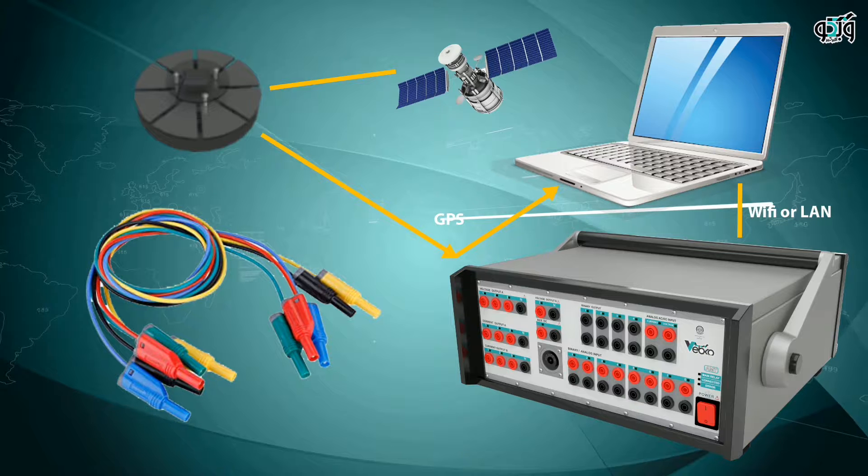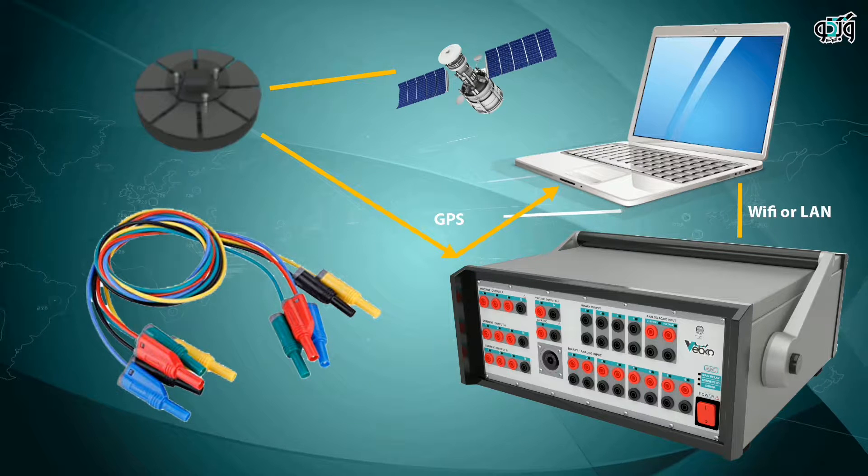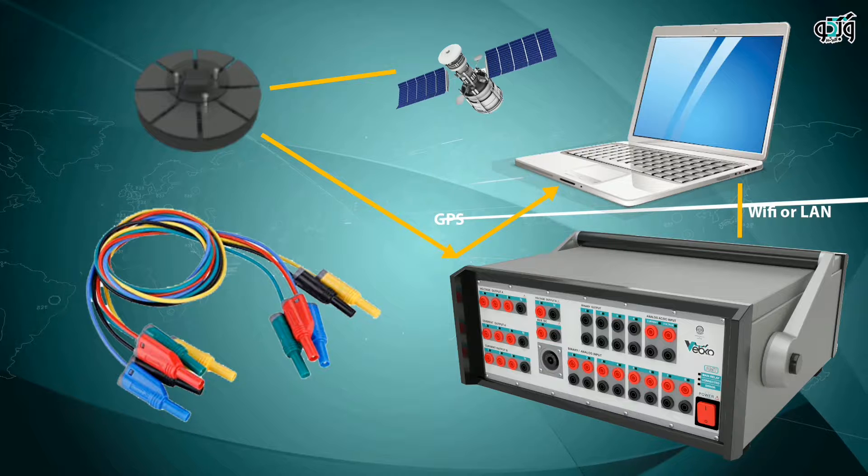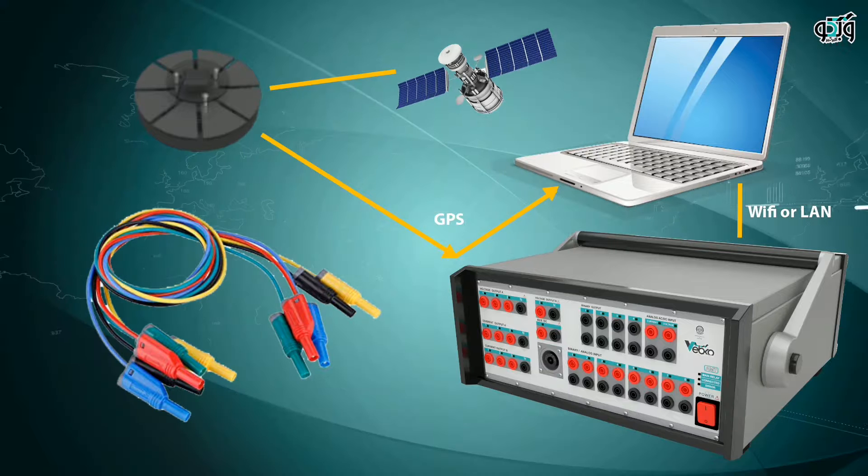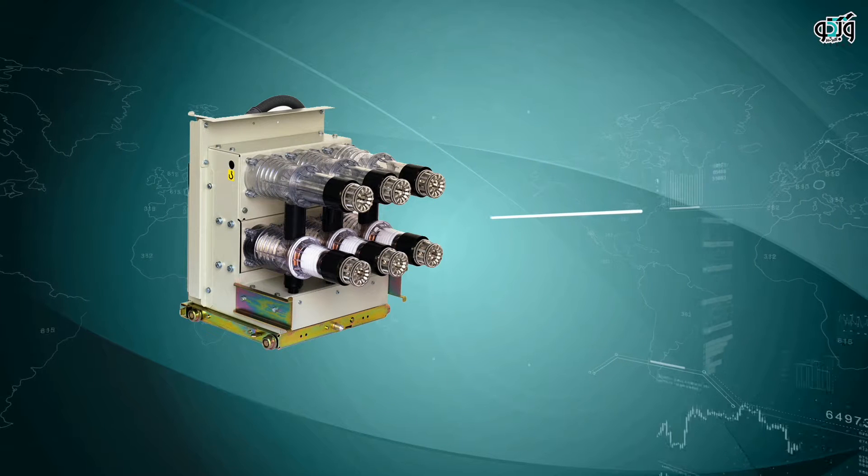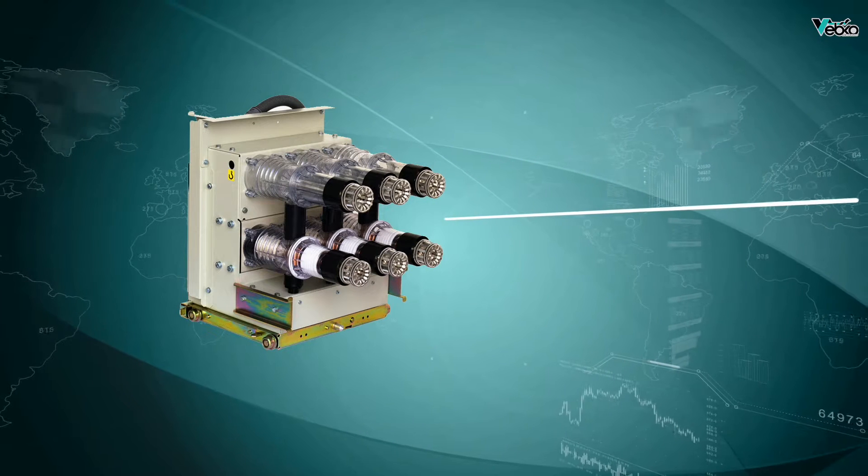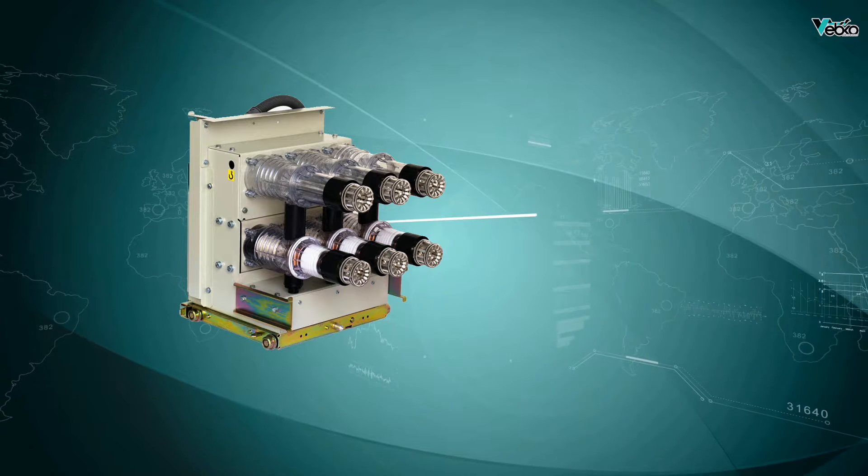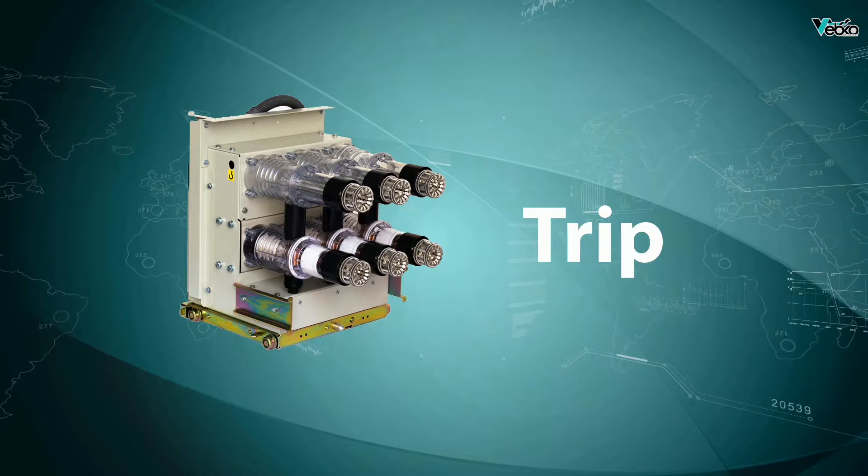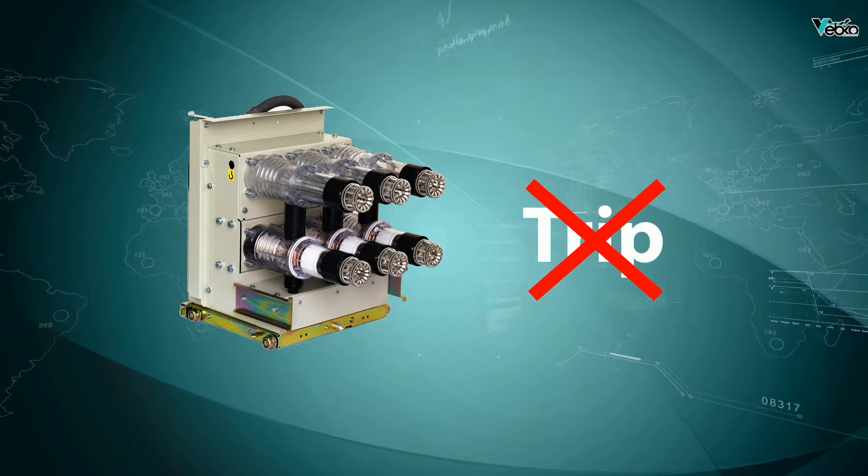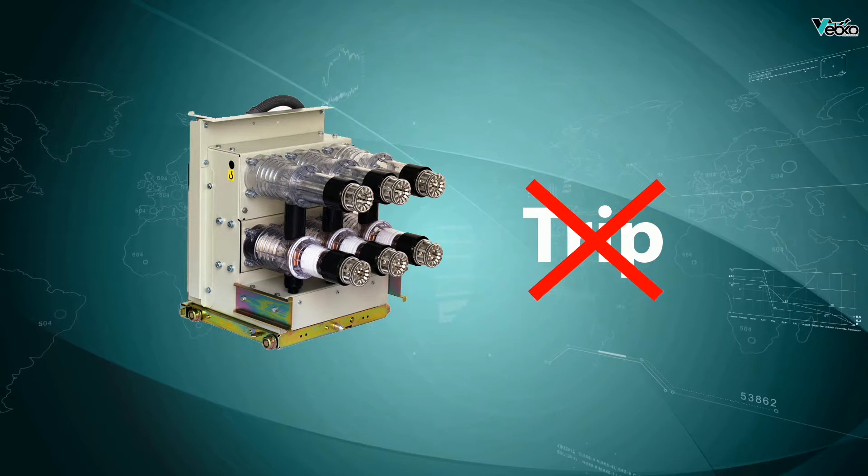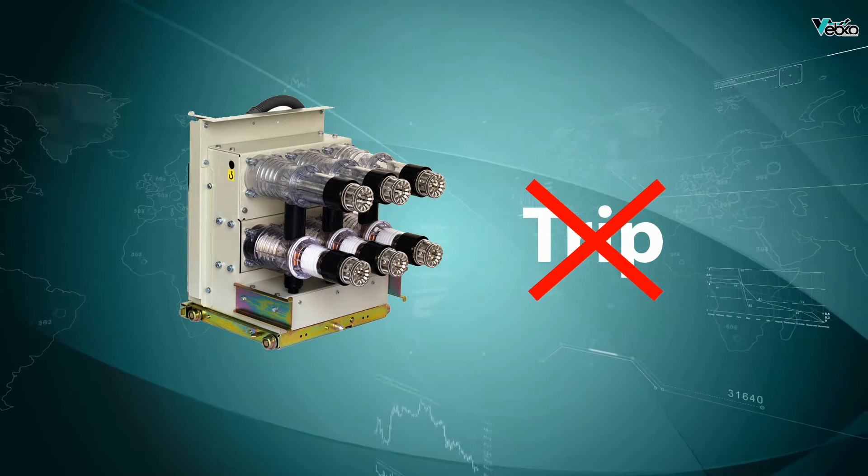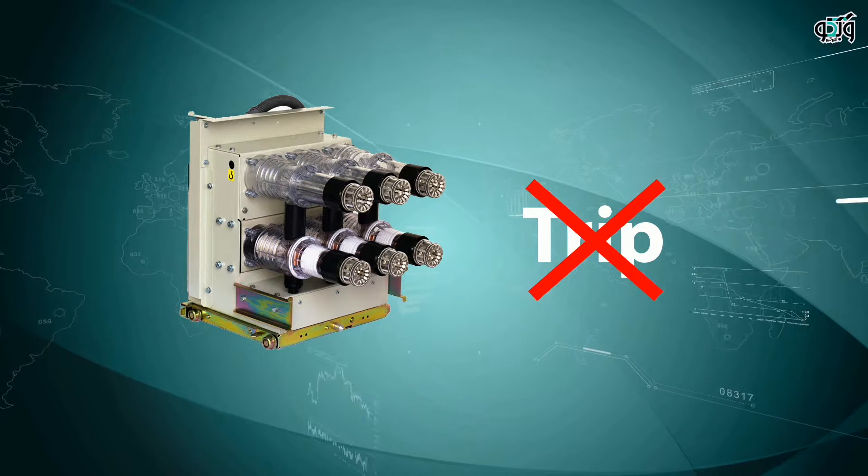In end-to-end tests, it is also possible to use other bases such as IRIG. To make sure that the breaker contact position is properly simulated by the test device, put the breakers in the right position. It should be noted that if other groups are working on the circuit breaker simultaneously, it is necessary to use the test block to make sure that no trip is going to go on the circuit breaker.